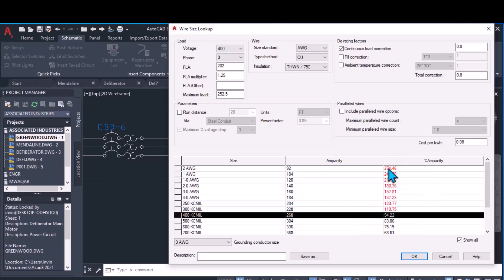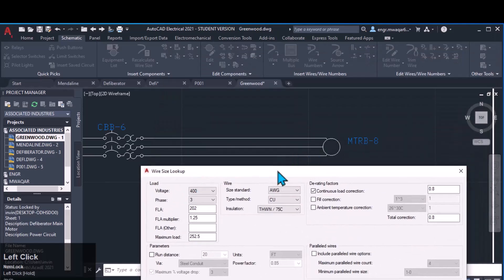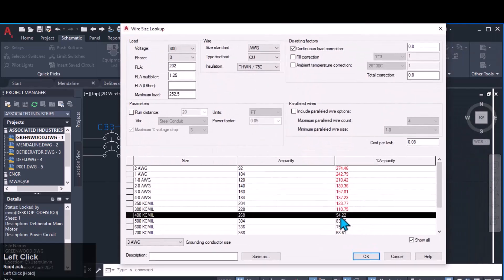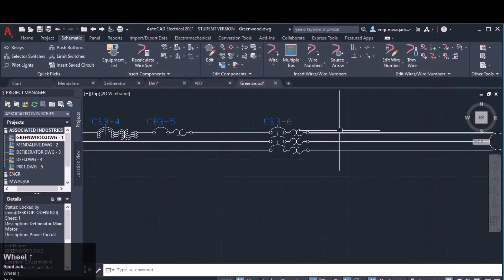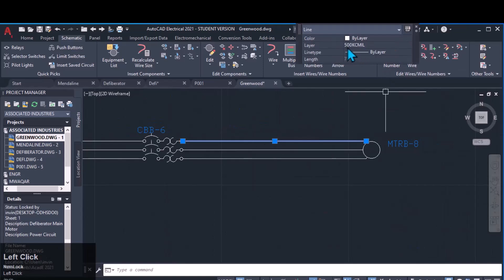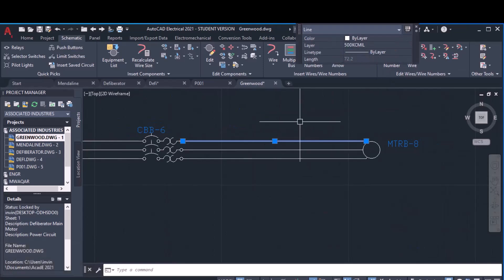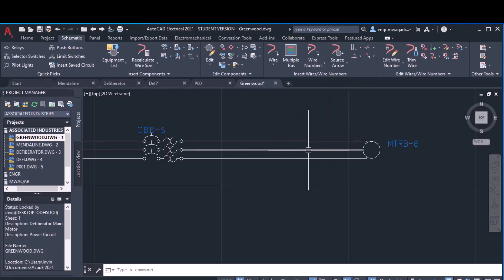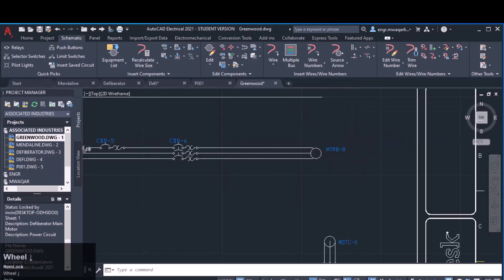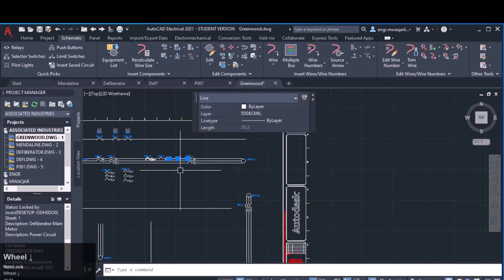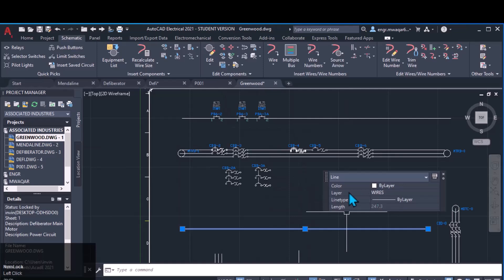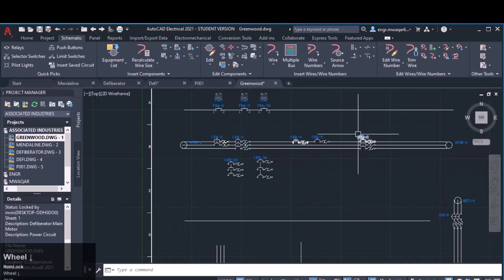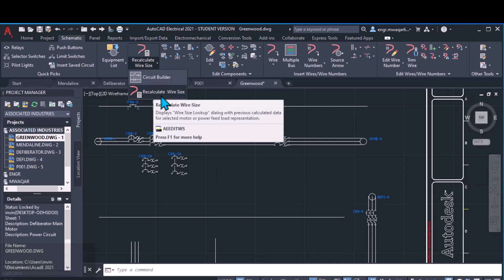The entries showing more than 100% are all red because those wires cannot be connected to this load. I have to pick one that fits — for example, 500 kcmil. Once entered, you will see the wire layers change to 500 kcmil. All three wires are automatically changed. If you click on this wire it is also changed to 500 kcmil — you can check that its layer is 'wire'. In this way we can adjust the size of wires, which is a very important feature in AutoCAD Electrical.